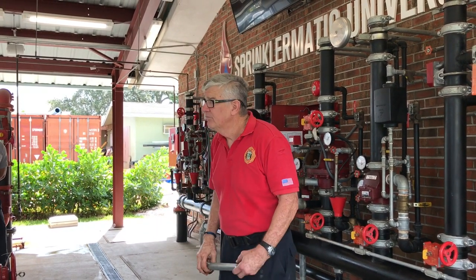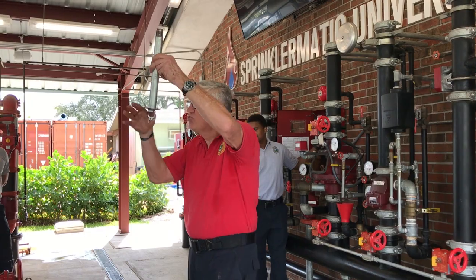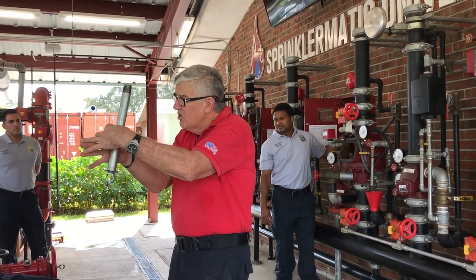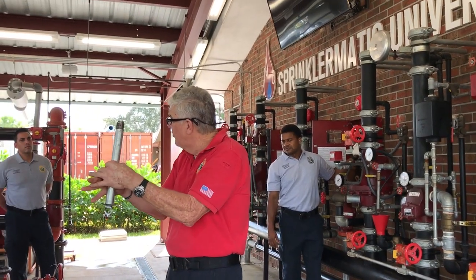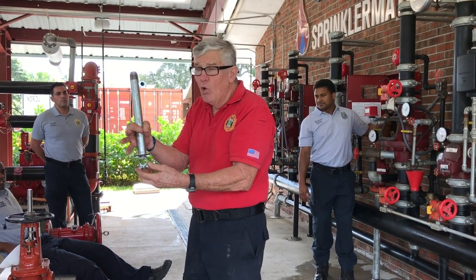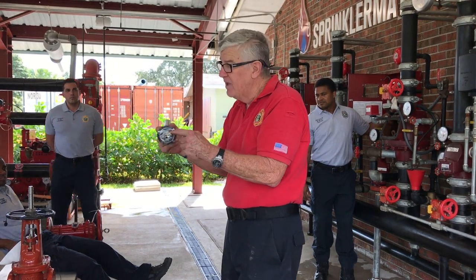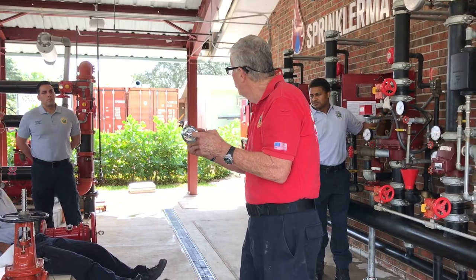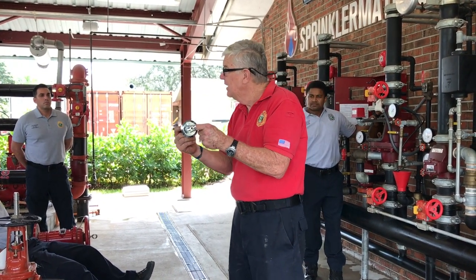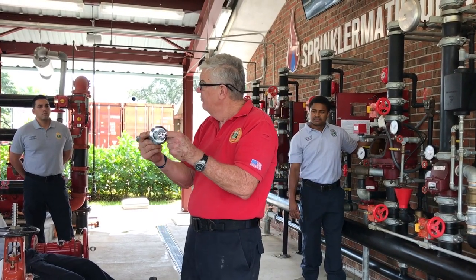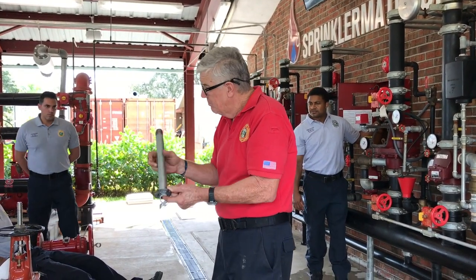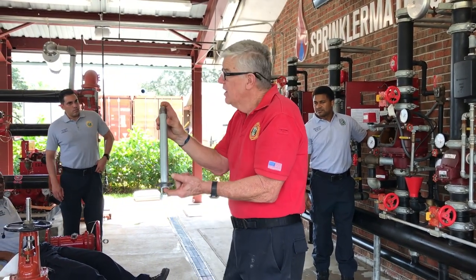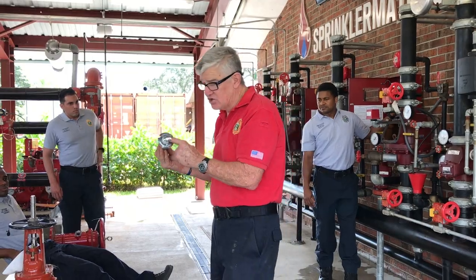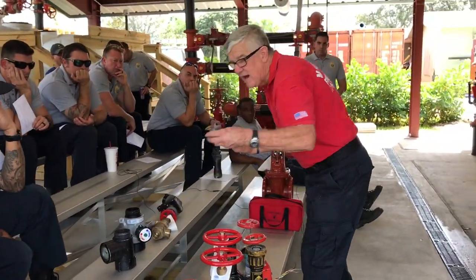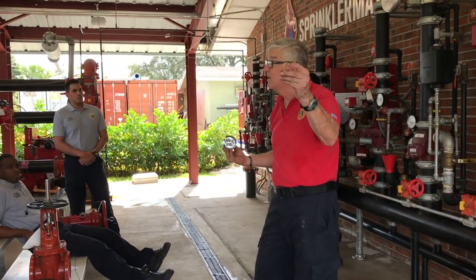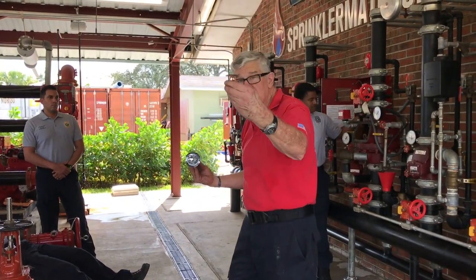Could we take a dry pendant head and drop it down into this cooler, insulate it extensively with polyurethane foam? Now, this is a sidewall head. So you might see this in an area to protect a balcony. It's cold. But what you have here is the ability to go into a freezing environment without having a dry pipe system, because you have a shaft in here. You have a plug on both sides. We all know that there is a plug that holds water back on a sprinkler head, and in this case, the plug is released by the activation of a heat-sensitive chemical.